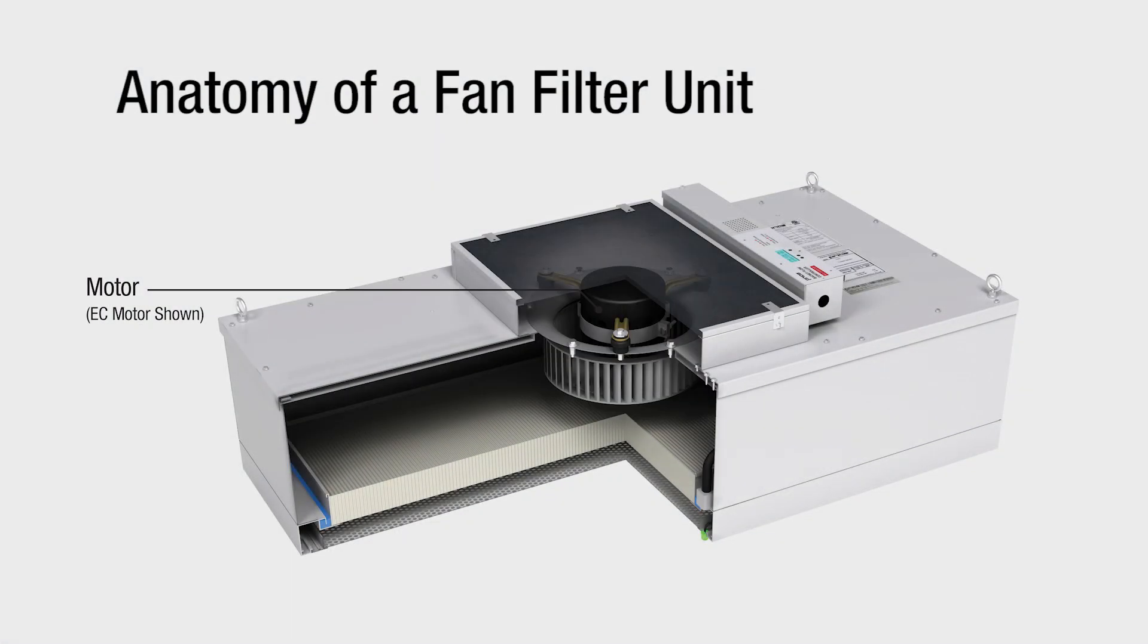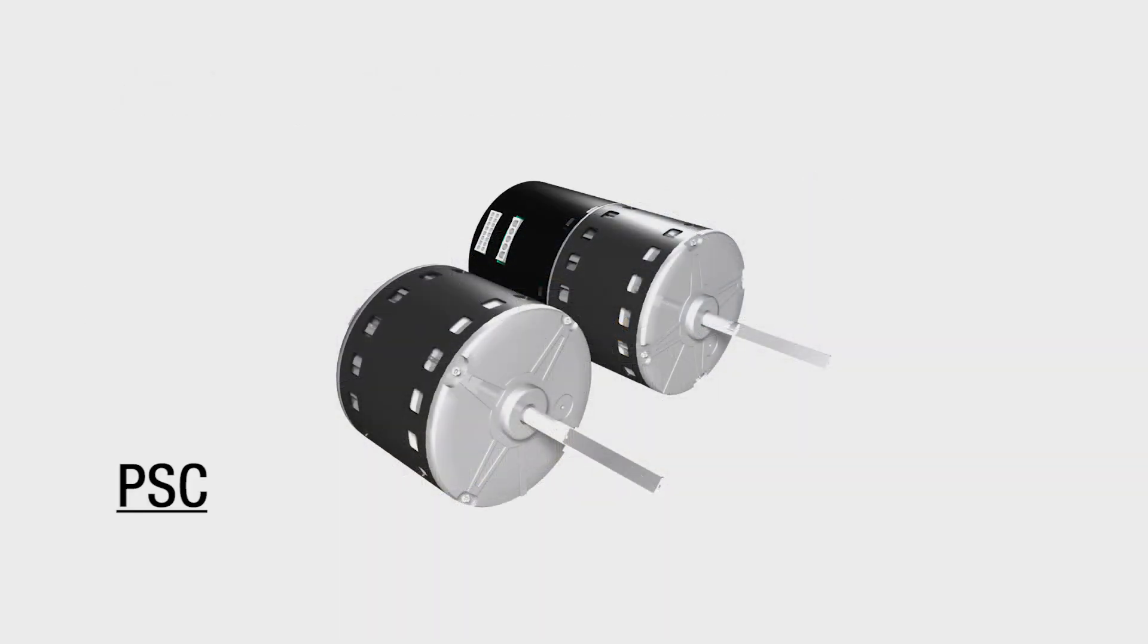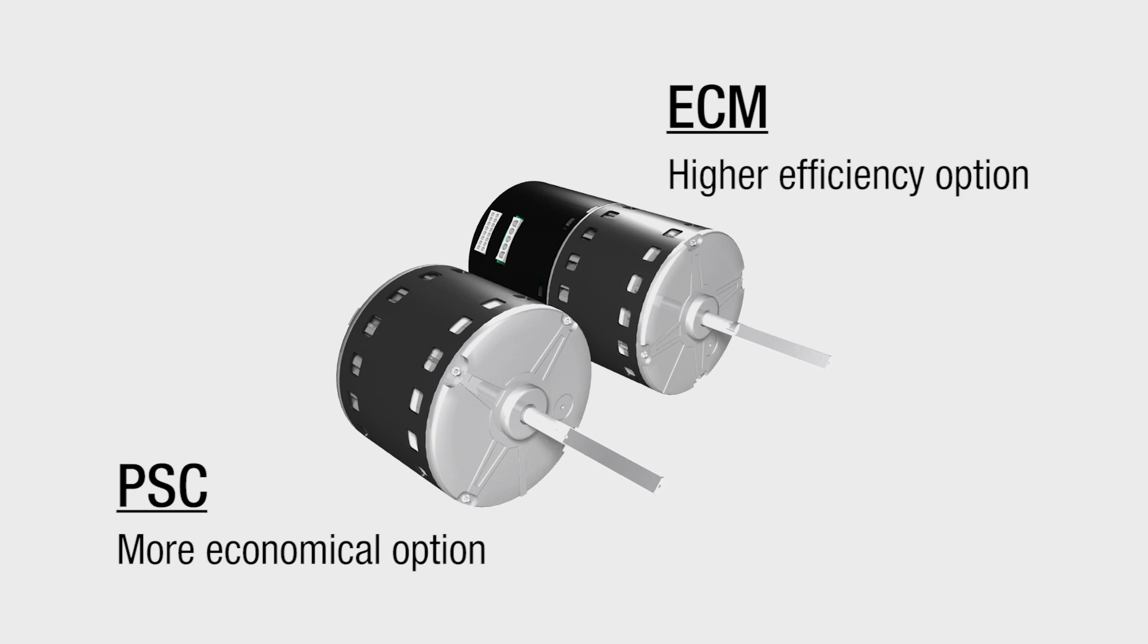Another option to look at when selecting a fan filter unit is the type of motor used. PSC or AC induction type motors are the more economical option. ECM or brushless DC motors are the higher efficiency option with onboard microprocessors that optimize motor performance and allow for motor programming.